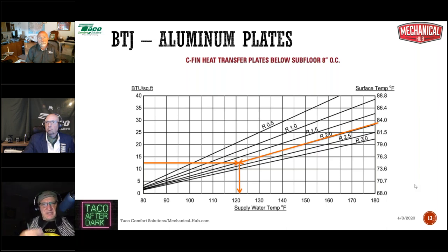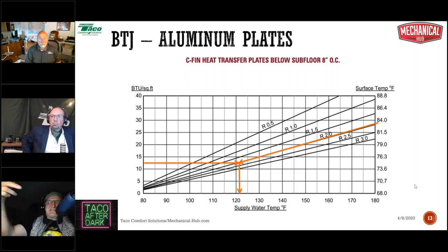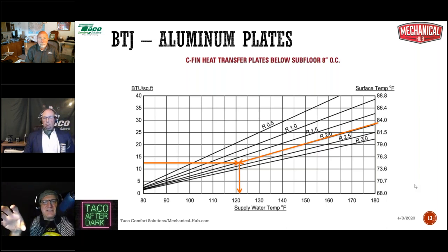The third stipulation that has to be met is that the required floor surface temperatures have to be similar. Same rule, different numbers, all right? They have to be close to one another. So 75 degrees on a floor surface temperature, we can go down to 72 and a half, or 73 maybe, 76 maybe, as long as they're consistent. If you've got 75 and 80, no, that's probably too much of a swing, or 72 and 80, that's too much of a swing. You can't zone those things together.